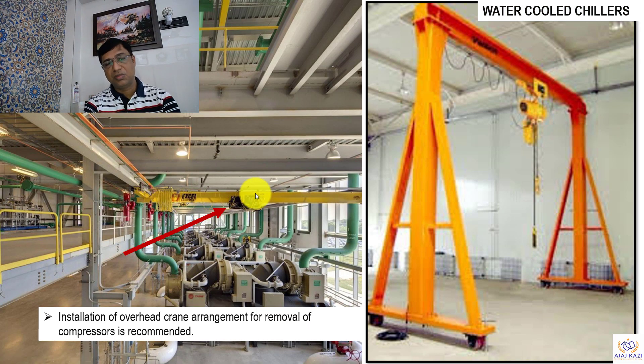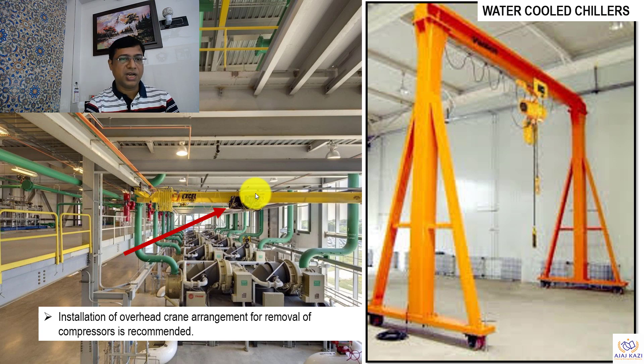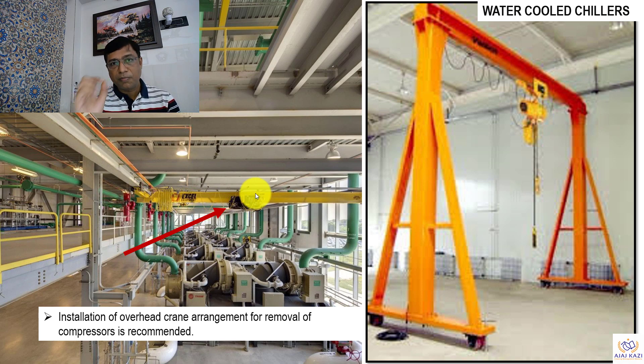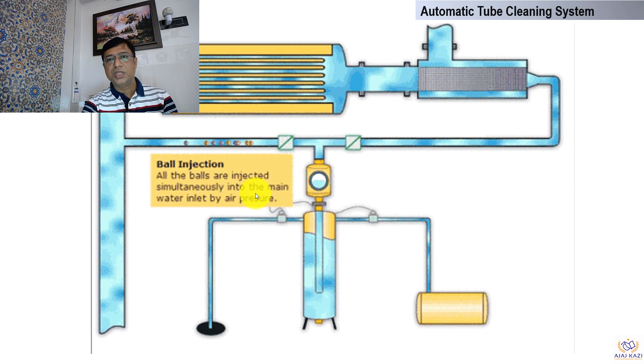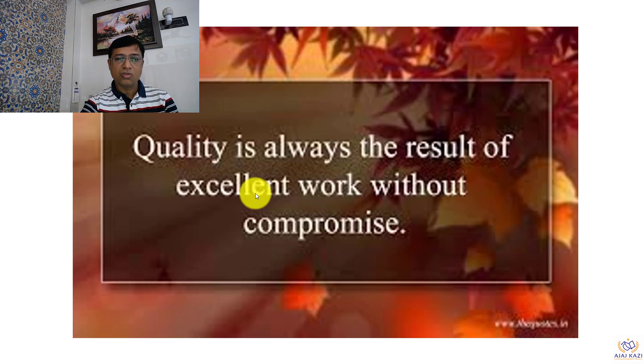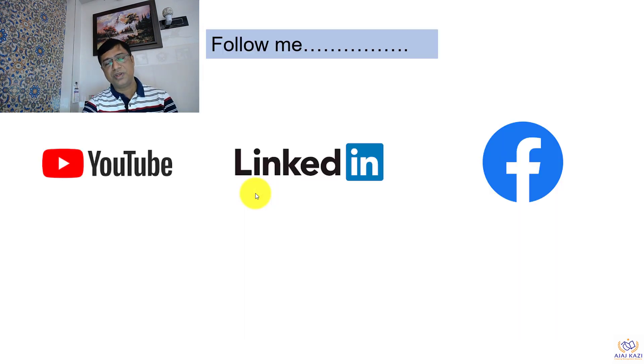Another important consideration is that chiller capacities are getting bigger and bigger. We need to plan how compressors can be taken out, which is why a crane arrangement installed at the plant room so that components can be quickly lifted for maintenance is another key element. We should also look at plant room layouts for chillers, including maintenance access for cleaning. There are automatic tube cleaning systems available as well. Quality is always the result of excellent work without compromise. I hope this has given you some value. You can follow me on YouTube, LinkedIn, and Facebook. Thank you very much for your patience.